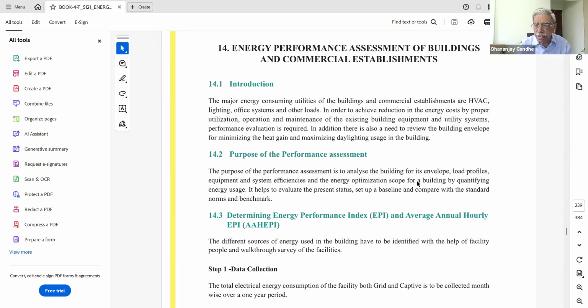Now, once a building starts operating and we start using various equipment, the HVAC system, lighting system and other systems, for existing buildings, what needs to be assessed every year is the performance. So let us go to the performance assessment. The purpose of assessment is to find out whether all the systems are working properly and efficiently, whether there is scope for reduction in energy consumption, and whether we can take some steps there. In order to assess the performance of the existing building, we need to analyze its envelope for the purpose of energy reduction. Also, what are the load profiles, especially the air conditioning system load profile and the electrical load profile.